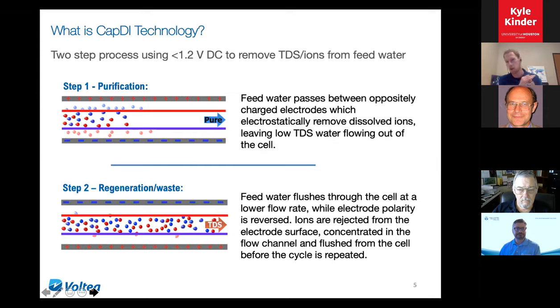We're not adding any chemicals, we're not adding any salts, like a salt-based ion exchange softener, where you regenerate it with a brine. We're just doing it with a small amount of electricity. The maximum voltage across that cell is 1.2 volts DC. I don't know if back in your school days you licked the end of a battery, but 1.2 volts isn't very much at all. By controlling the flow rate between purification and regeneration, we aim to recover about 85%, if not more, of the water that we're treating. So we make sure we get as much water as possible treated into your process and minimize and concentrate up what's going to drain.